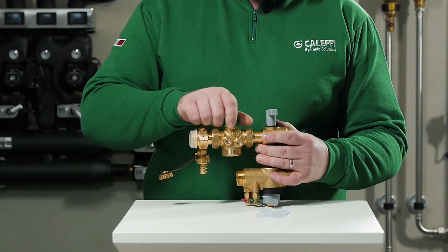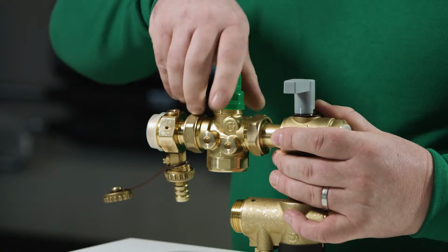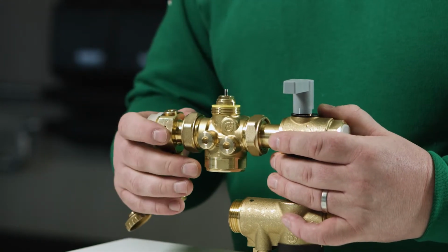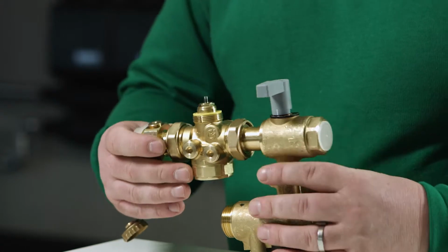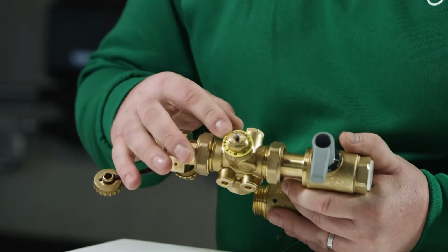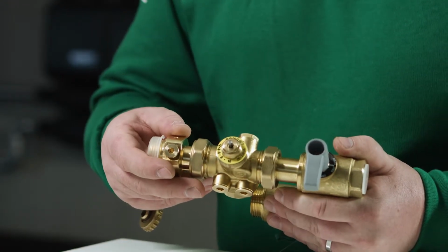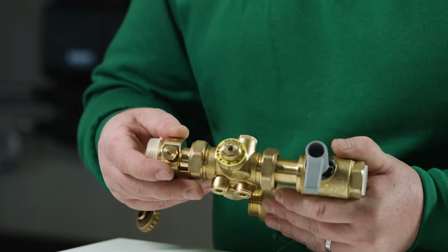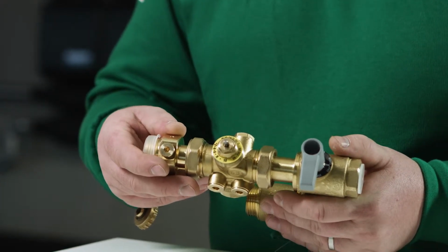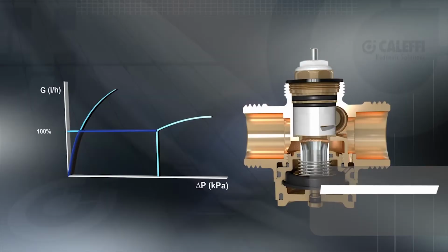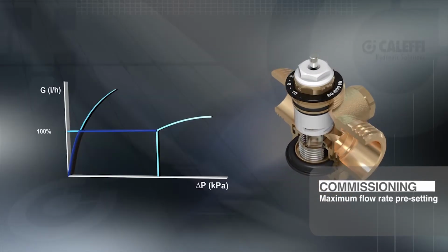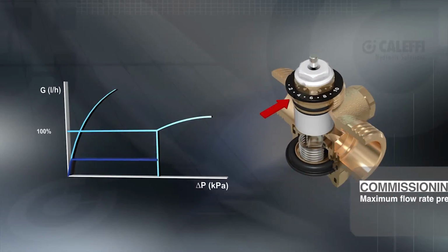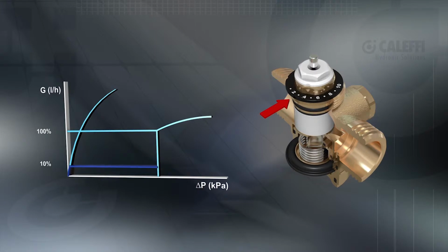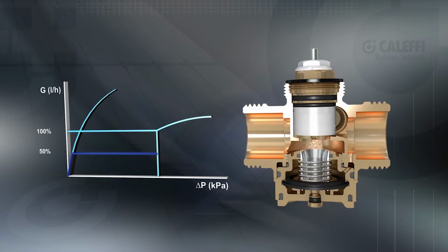This is achieved by unscrewing the plastic cap. This then gains access to the adjustment knob. This is adjusted using a hexagonal spanner. There is a scale from 2 to 10 on top of the valve. Each number indicates the desired flow rate through the terminal unit. Using the adjustment scale for indication, we can now set the desired flow rate through the PICV. Each number on the scale adjustment relates to a presettable flow rate.